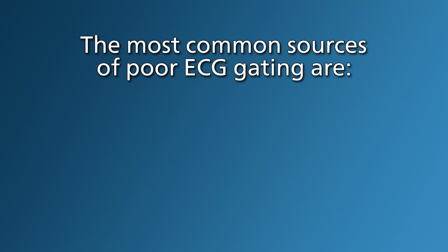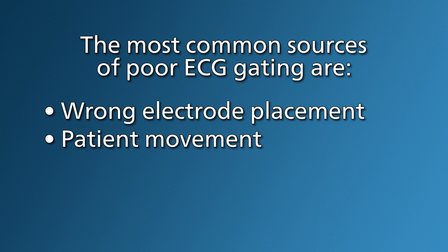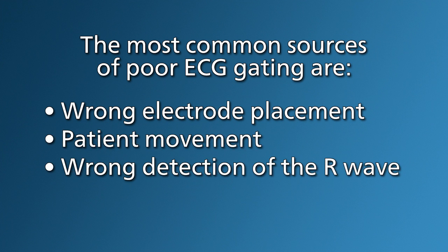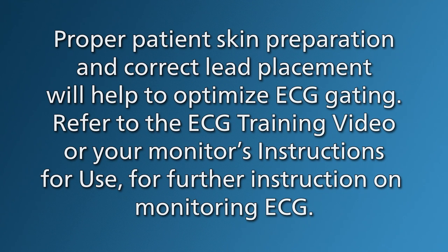The most common sources of poor ECG gating are wrong electrode placement, patient movement, or wrong detection of the R wave. Proper patient skin preparation and correct lead placement will help to optimize ECG gating.